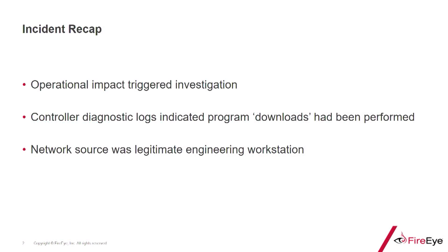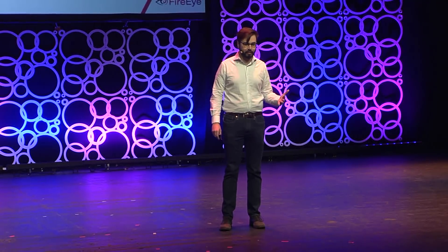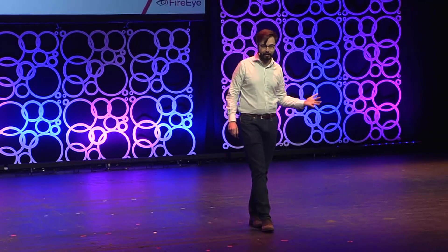To get started, the incident itself — just a brief review of the sequence of events. An operational impact, specifically the failure into a fail-safe mode of two Triconex safety instrumented system controllers within a critical infrastructure facility, triggered an investigation — primarily an investigation of an outage, not necessarily of a cybersecurity incident.